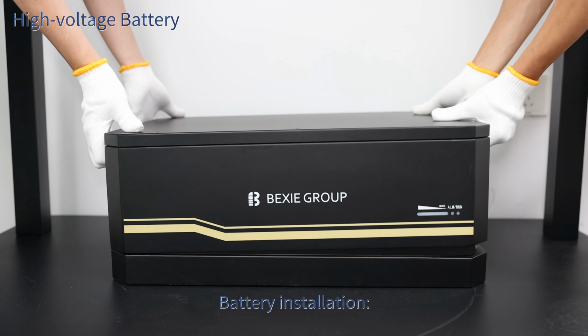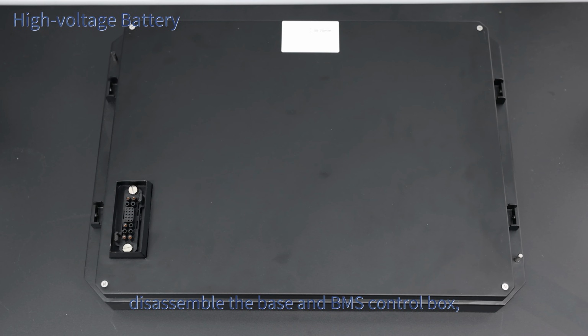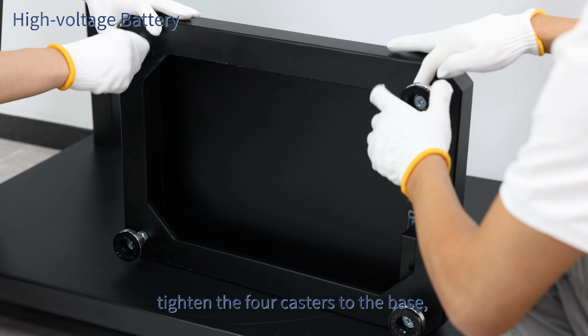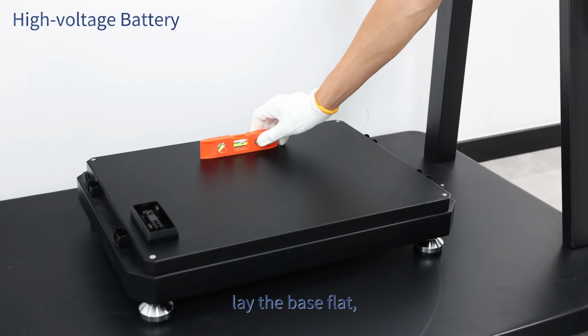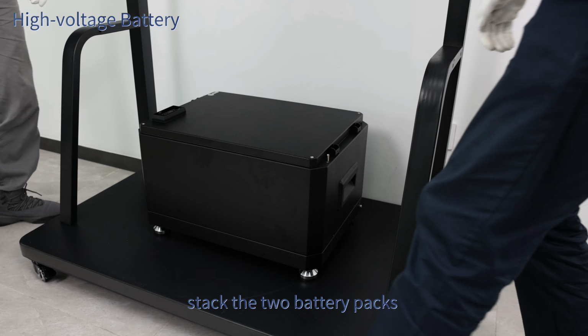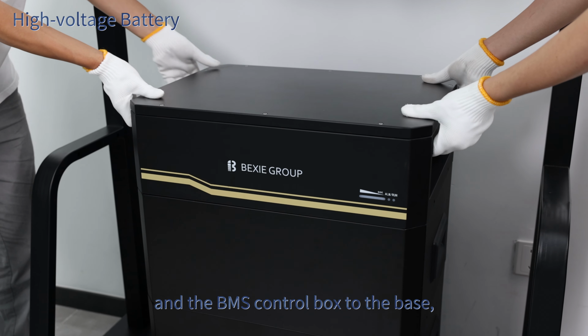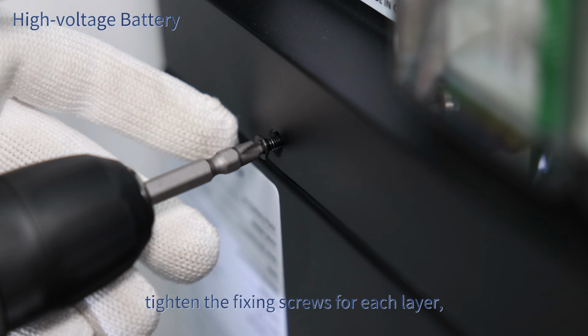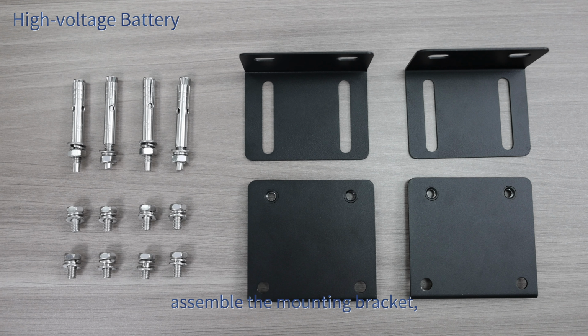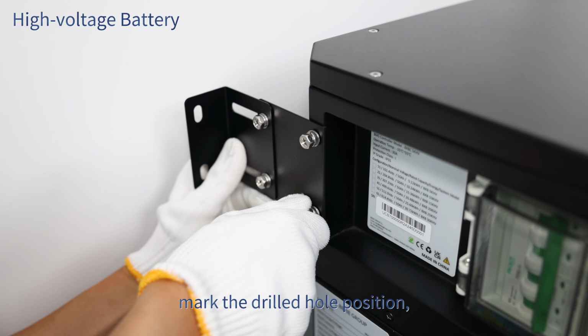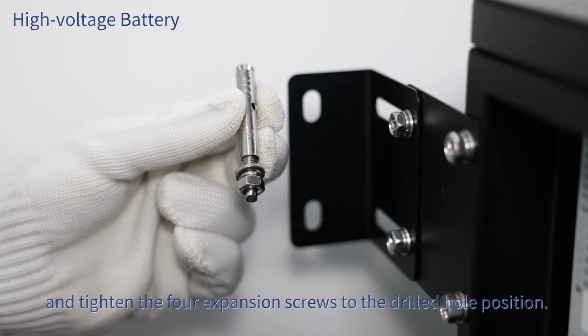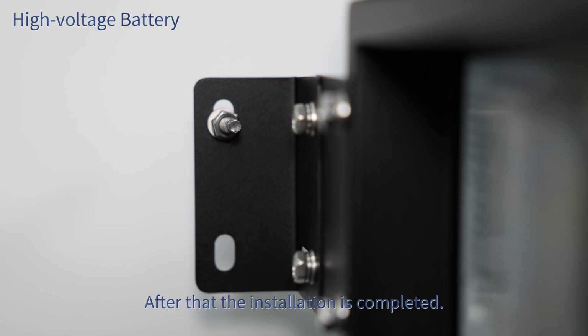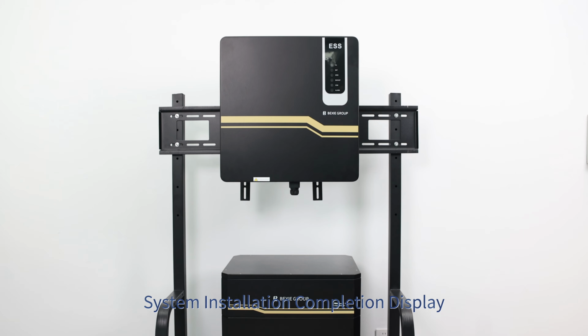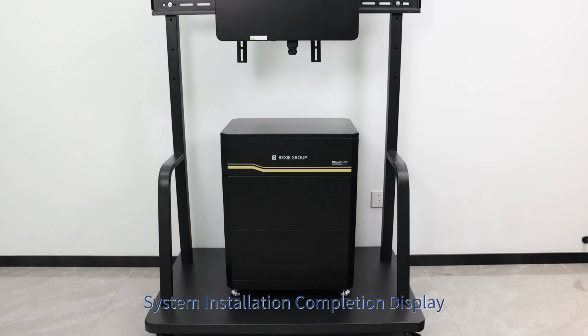Battery installation. Disassemble the base and BMS control box. Tighten the 4 casters to the base. Lay the base flat. Align the quick plug terminals. Stack the 2 battery packs and the BMS control box to the base. Tighten the fixing screws for each layer. Assemble the mounting bracket. Mark the drilled hole position and tighten the 4 expansion screws to the drilled hole position. After that, the installation is completed. System installation completion display.